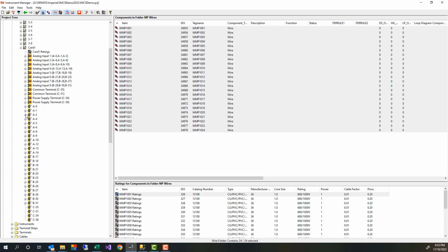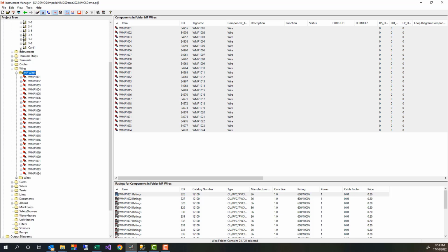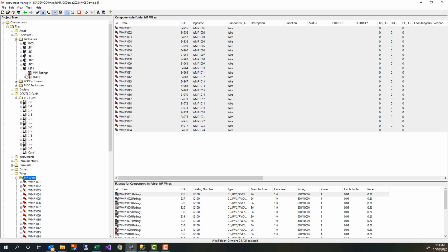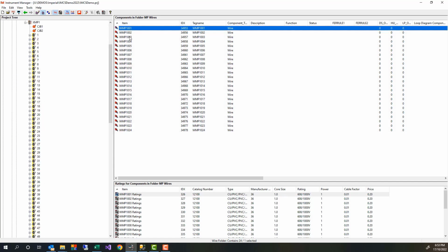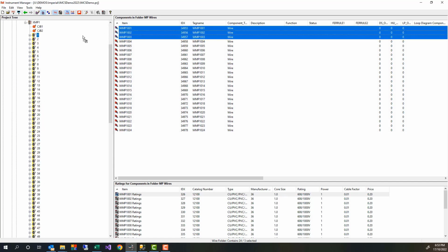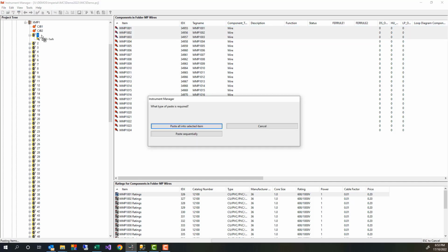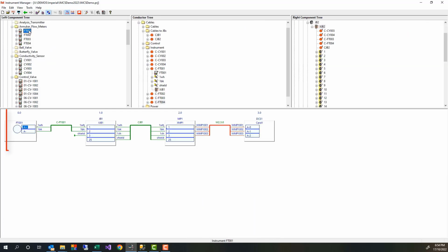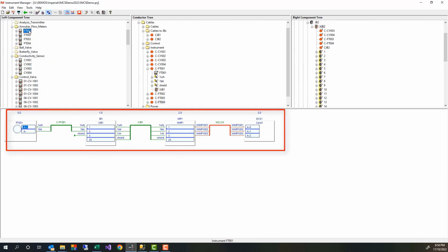This connects the wires to terminals in sequence with their tree position. Again, you can make these terminations individually if you wish. The other end of these wires is connected to the marshalling panel terminals. I will connect these 3 wires at a time, selectively cross-wiring them to the desired instrument. I will now preview my loops. With the red wires now present, they look complete.